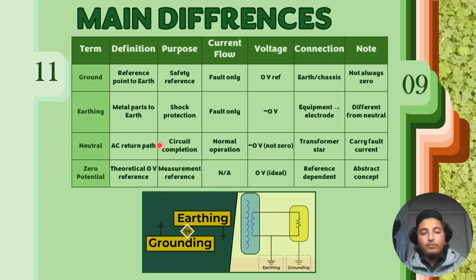Now the main difference between ground, earth, neutral, and zero potential. First, definitions: ground is a reference point to the earth, earthing is the metal part exposed to the earth, neutral is a return path in AC and DC systems, and zero potential is theoretically a 0 volt reference. Purpose: grounding is for safety, earthing is for shock protection, neutral is for circuit completion, and zero potential is a theoretical measurement reference.